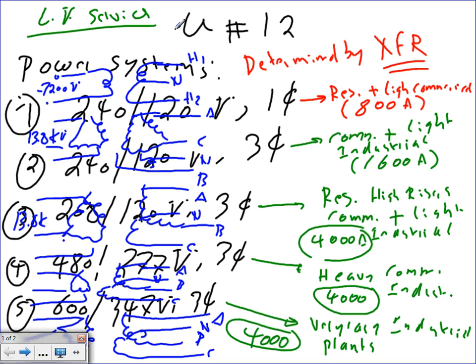Any question? This is one type of transformer. 1 coil, 1 phase. So we did mostly, guys, light commercial, residential. You move to industrial, commercial, you move to 3 phase. Any question, guys, about transformer number 1 or service number 1? And these are called low voltage services. Anybody know what a low voltage service is? Because all the voltages on the secondary side, not the primary, are less than 600 volts. These are low voltage services.